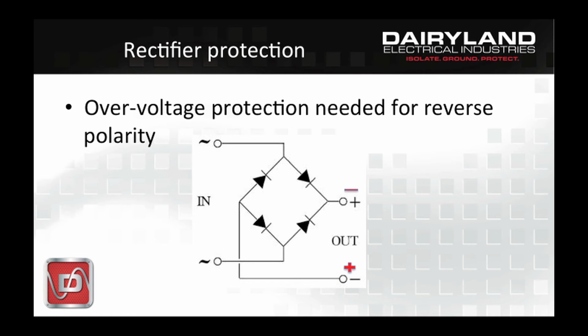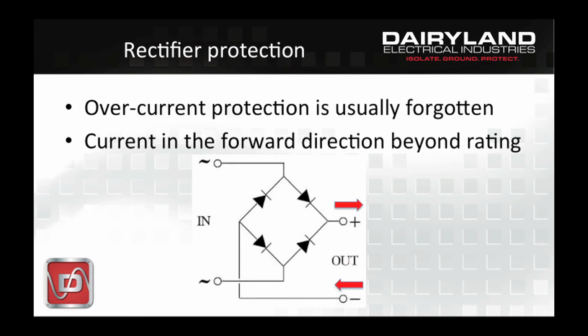Well, overvoltage protection on rectifiers is needed for the reverse polarity on the diode stack. If the diodes in the stack had an opposite polarity of a high magnitude applied to them, that's where you can fail the diode electrically, and that would be the end of the rectifier. So overvoltage protection is needed for that reverse direction. One thing that's often forgotten is that in the forward bias direction for rectifiers and diodes, the issue isn't reverse voltage, it's already in conduction. It's overcurrent. So when the forward bias diode has current beyond what it's rated, it could also fail.